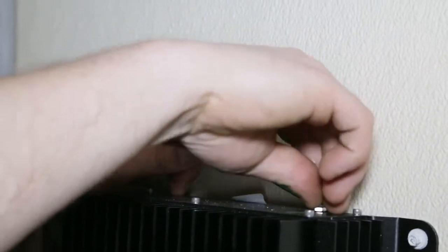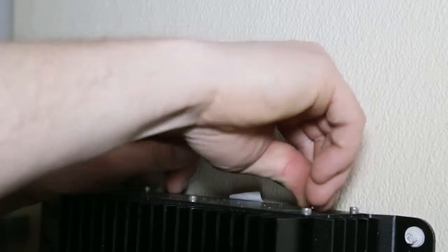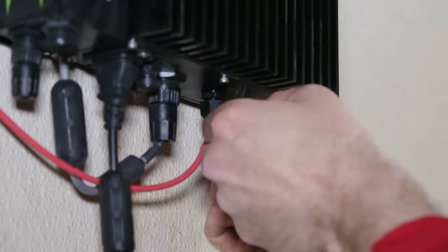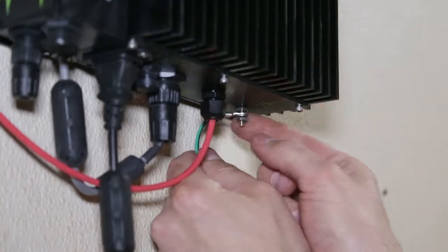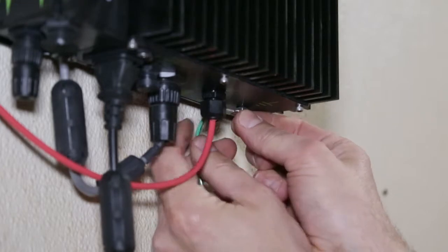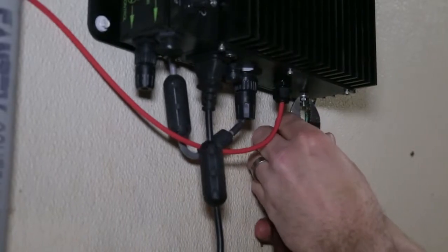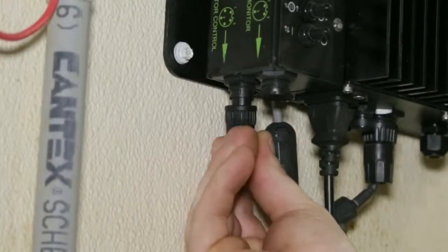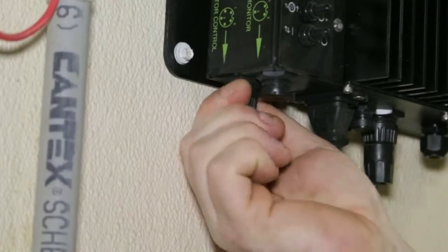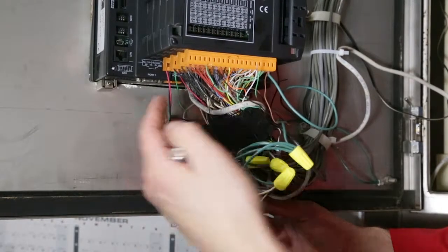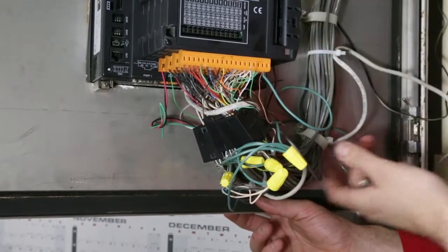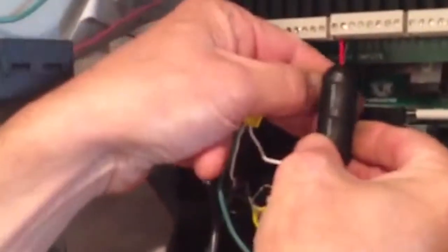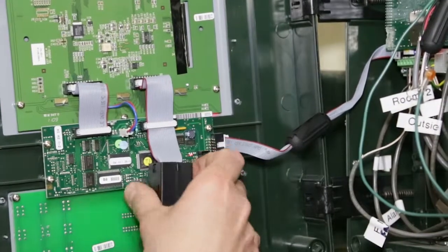Attach a ground wire to the ground stud of the power supply and connect it to the AC electrical ground. There are 2 ground studs on each power supply. Attach a ground wire to the ground stud of the power supply and attach it to the ceiling or other metal material that connects all rooms energized by the power supply. Install the non-automation caps and the 5 pin connector. All computer equipment, controllers, and other sensitive equipment must be grounded properly prior to energizing the power supply. Also ferrite collars must be installed on probe wires prior to energizing the power supply.